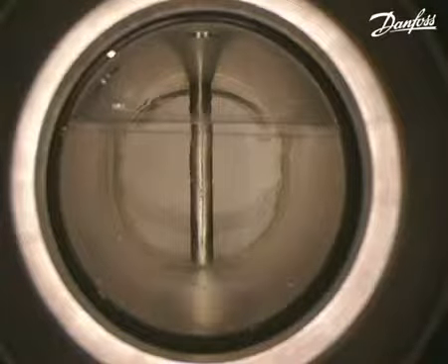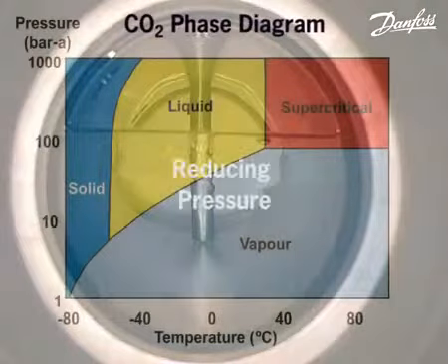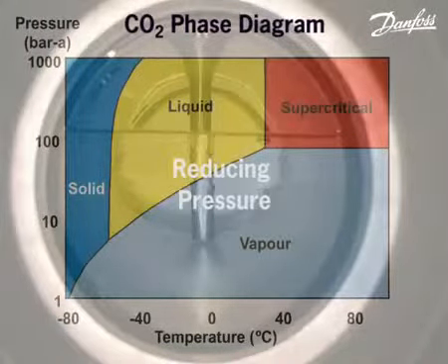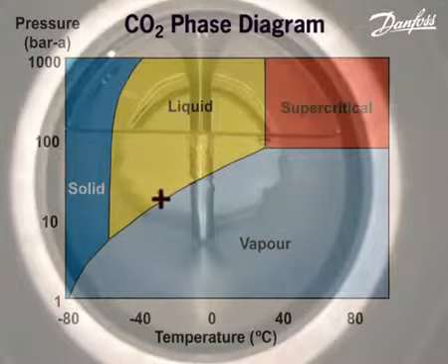The vent valve is now opened to release CO2 vapour. The pressure and therefore the temperature of the liquid CO2 falls rapidly as it boils to produce more vapour.